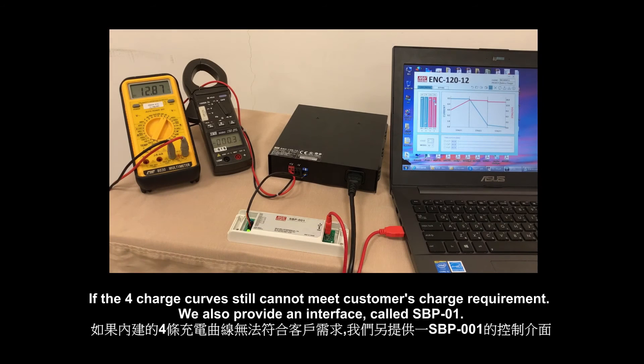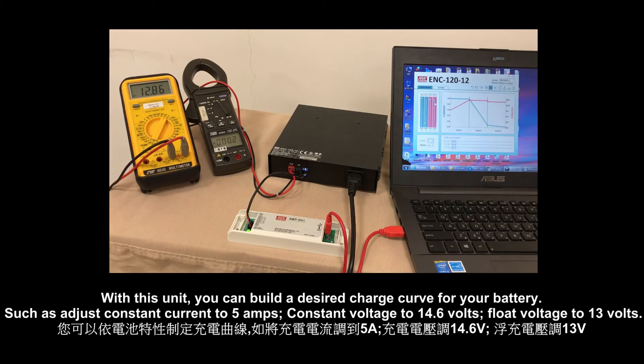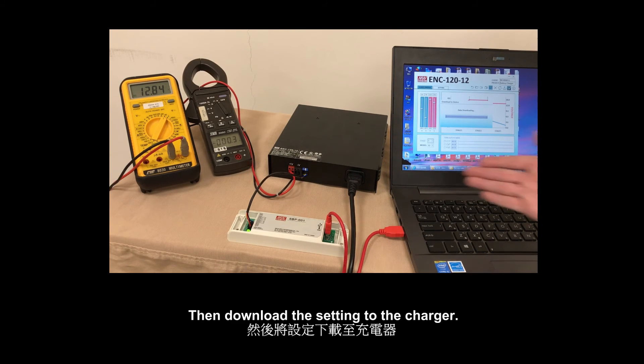When the charge curves still cannot meet the customer's charger requirement, we also provide an interface called SBP-01. With this unit, you can build a desired charger curve for your batteries, such as adjusting constant current to 5A, constant voltage to 14.6V, and float voltage to 13V. To accelerate the test, I adjust the stop current to 2.4, then download the setting to the charger.